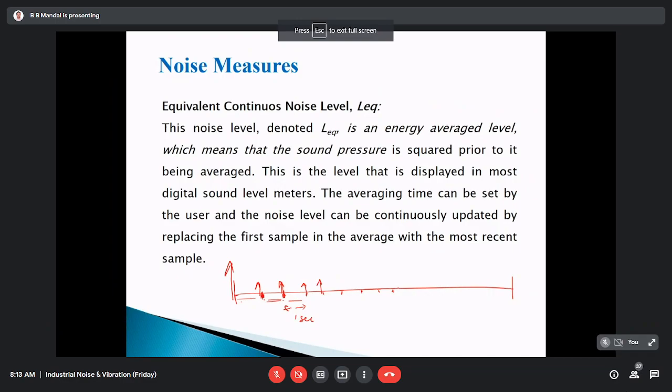The option is there. But here what we do is, for every second we are averaging this part and displaying. So what happens is that every 1 second, when we switch on and it starts counting and displaying, then at every 1 second you will see something like 77.8. Next 1 second you may see 77. Like that, it goes on fluctuating every second.